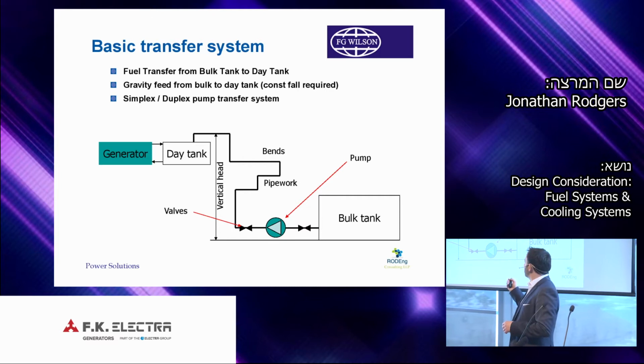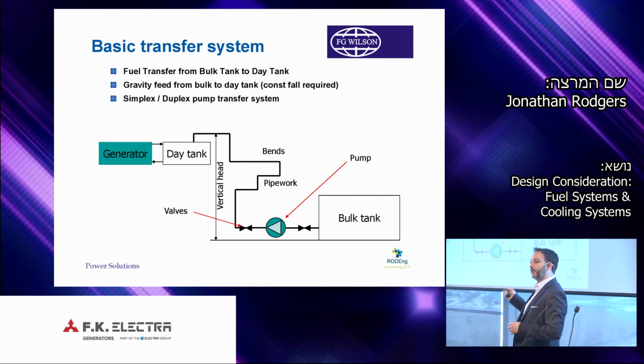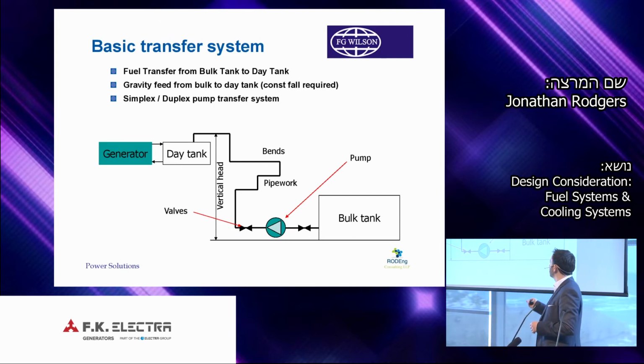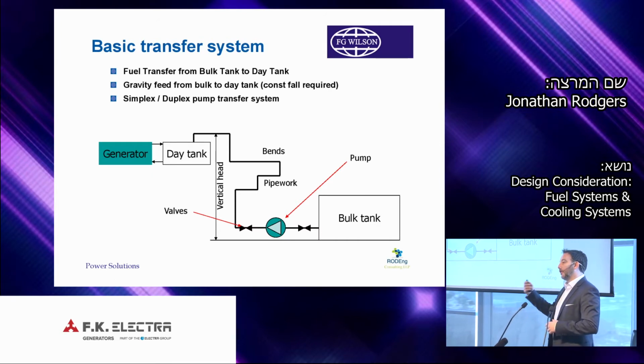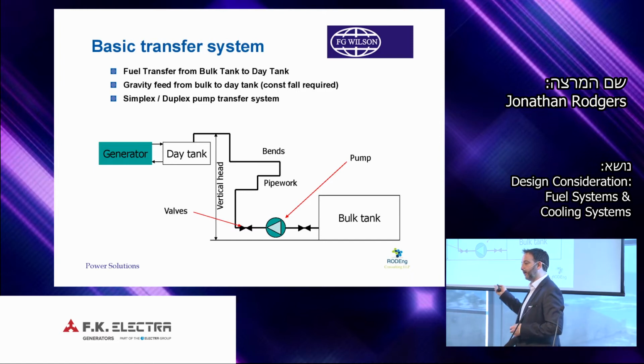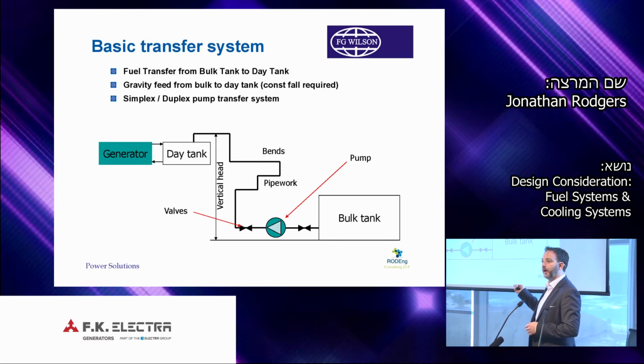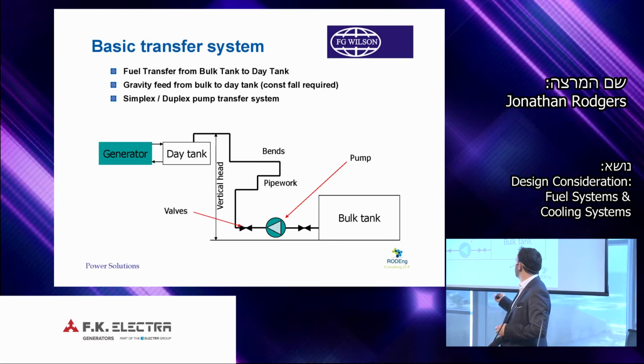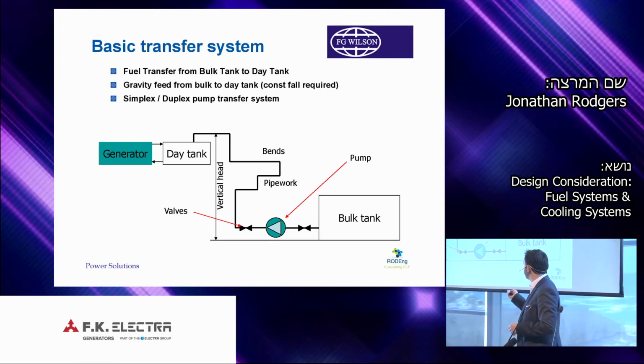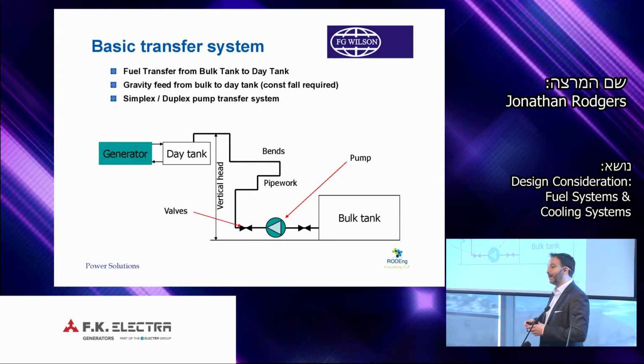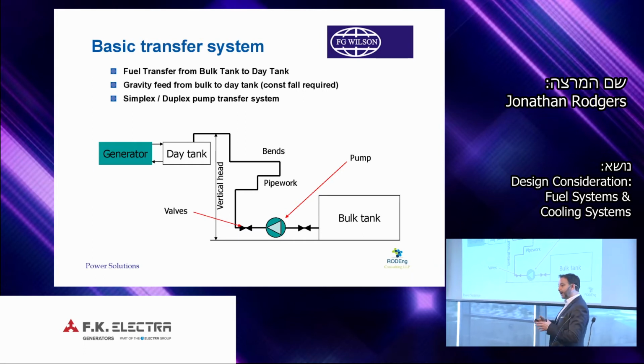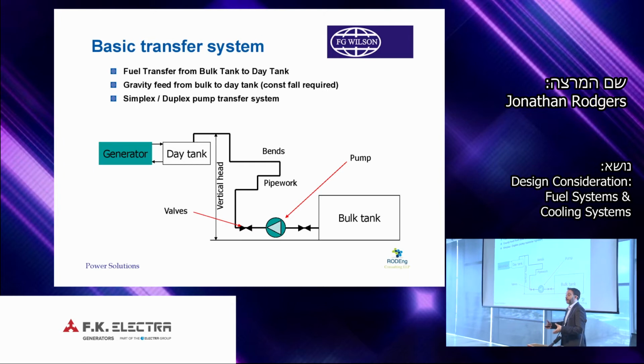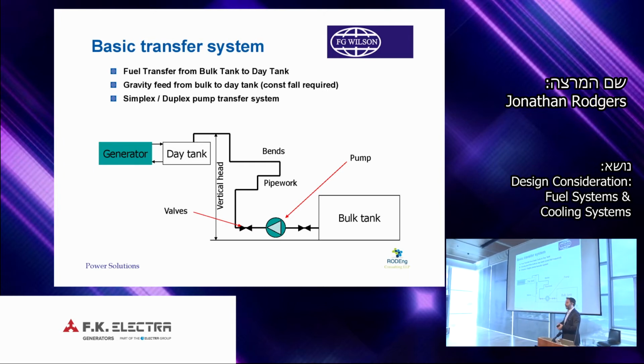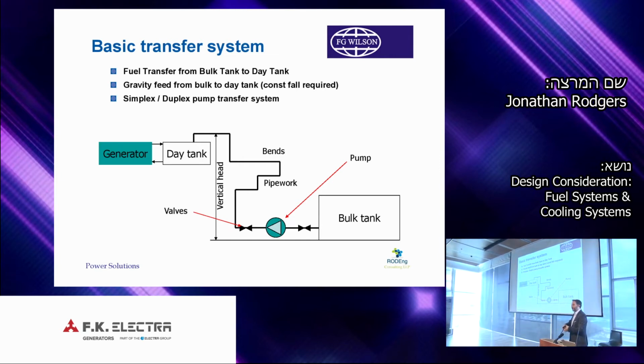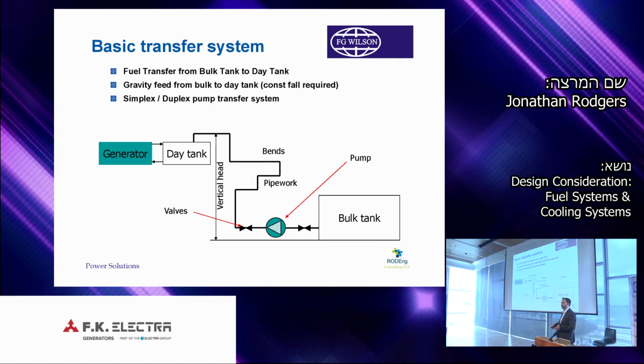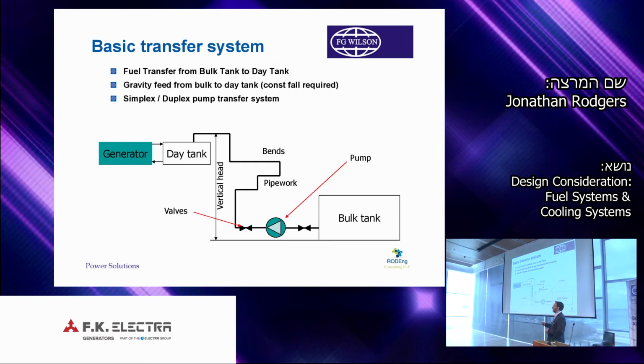So just to look in more detail, when we're looking to size the system and to have a fuel transfer from our bulk tank to our day tank, we look at the route of the pipework. Normally, we will have to pump between bulk tank to day tank. This is a preferred way because we can control the pressure to the day tank. And when we're doing this, we will look to size this pump based on the number of bends within the pipework and the length of pipe. We do pump sizing calculation for the pressure and sizing of the pump. In that, we decide on the pipe size, so the diameter of the pipe, to ensure we have a balanced pressure at the correct fill rate for transferring. So we do these calculations. They can be provided through F.K. Electra as well.